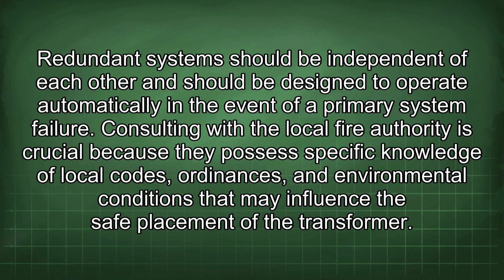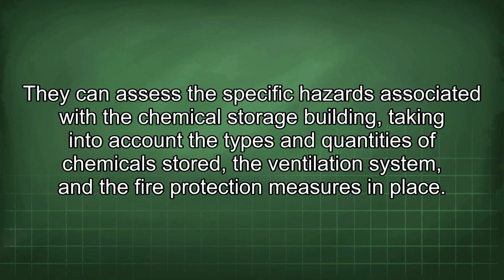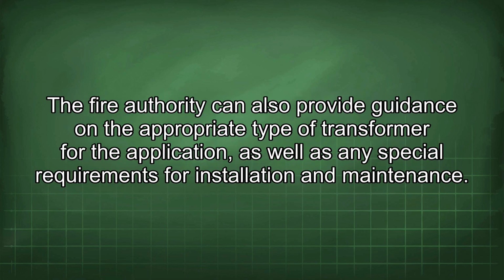Consulting with the local fire authority is crucial because they possess specific knowledge of local codes, ordinances, and environmental conditions that may influence the safe placement of the transformer. They can assess the specific hazards associated with the chemical storage building, taking into account the types and quantities of chemicals stored, the ventilation system, and the fire protection measures in place. The fire authority can also provide guidance on the appropriate type of transformer for the application, as well as any special requirements for installation and maintenance.